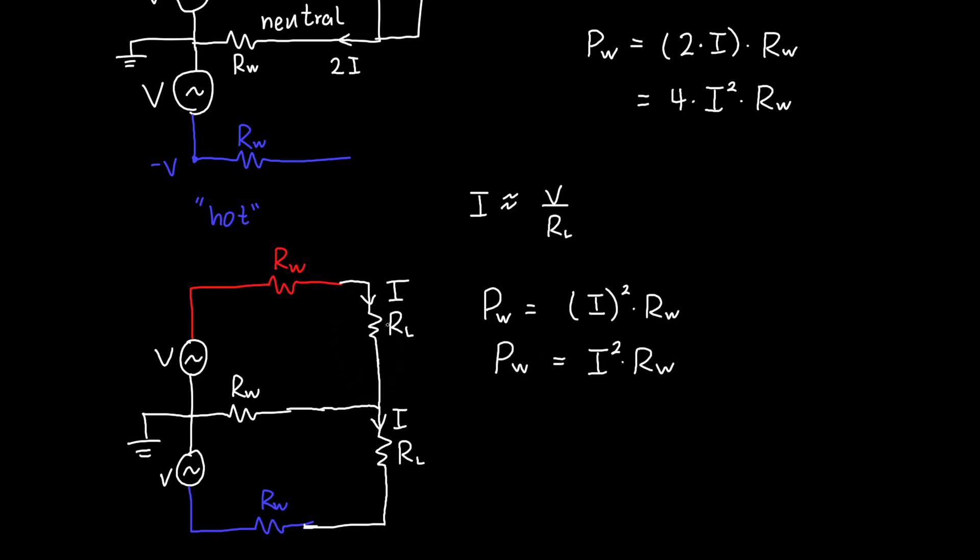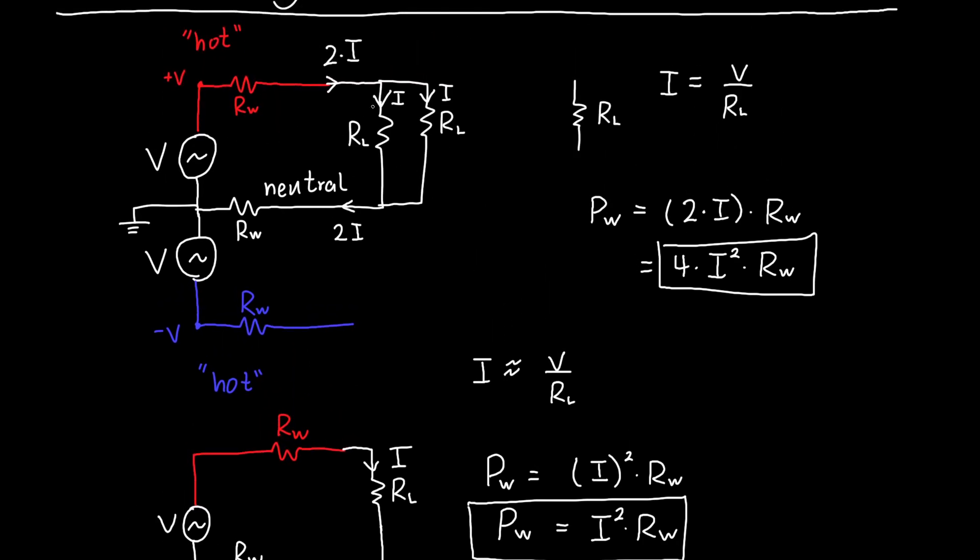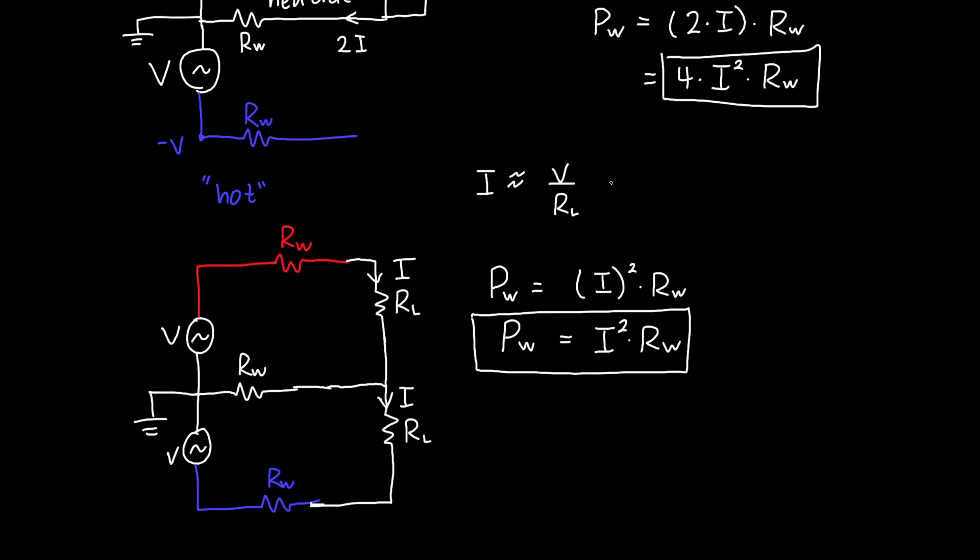So the power is I² times RW. But look at this—in the case where we have one on the top and one on the bottom, our power dissipated in each wire is a quarter of that in the case where we had both loads on the same circuit. This means we have less power dissipated in our wires.